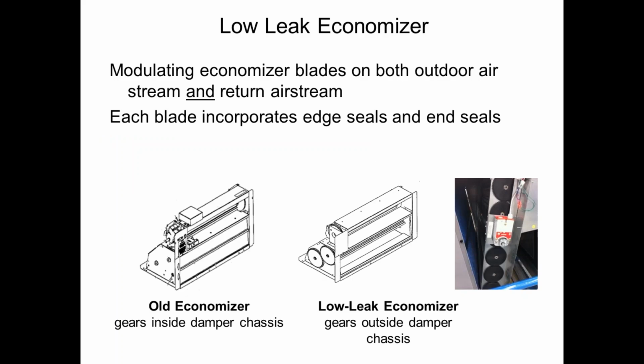Basically, with low leak, there's a couple major changes that happen. One is, we put the basic seals on the damper, the leading edges of the damper and on the sides, the blades. But the other major difference is that the gears, which historically have been inside the airflow path of the economizer, now have to move to the outside because the gears have to be able to move. Hence, if they can move, there's some ability for air to get through them. So having them on the inside airstream was not really helping us in terms of leakage. So now the gears have moved to the outside. Generally speaking, you can tell your rooftop supplier that you need a low leak economizer, and if you just say those keywords, low leak, they should know exactly what you're talking about, especially if they're in a state that follows the code. If they don't know what you're talking about, have them call me.